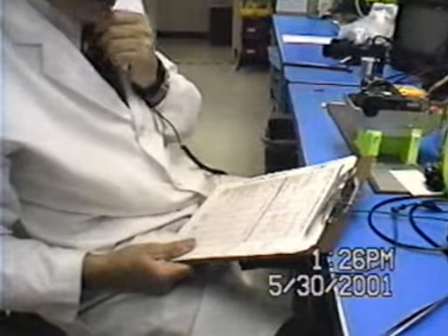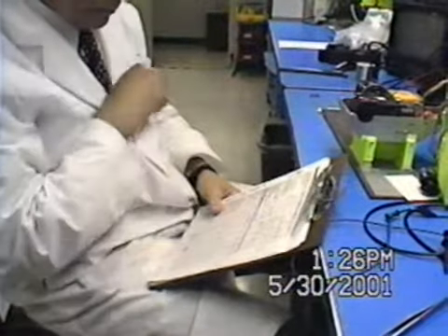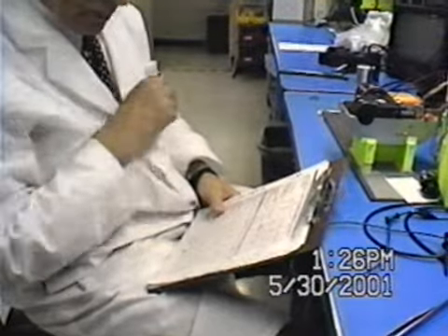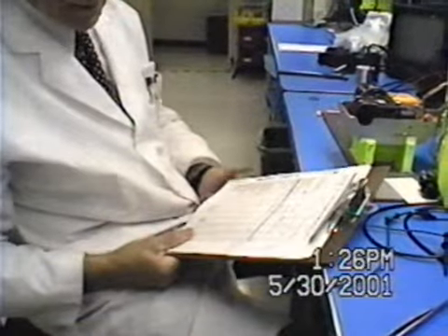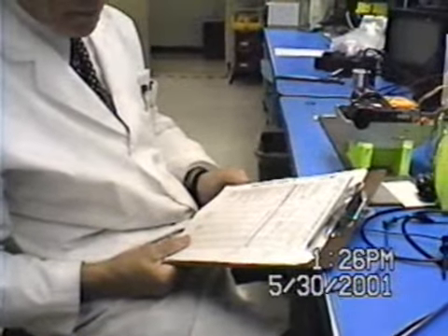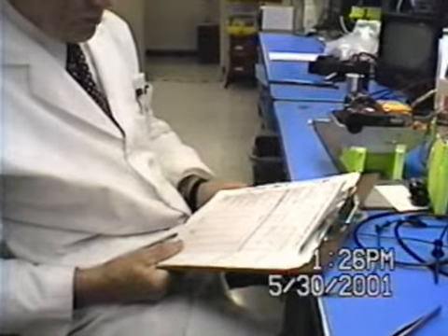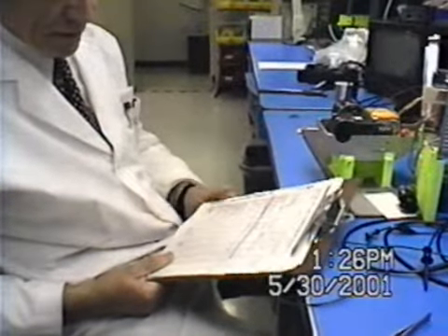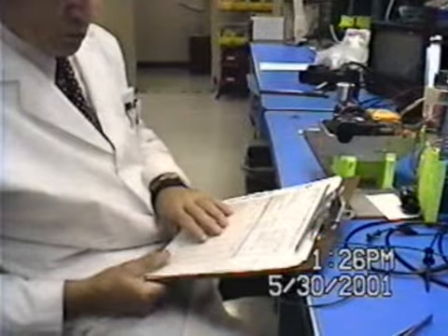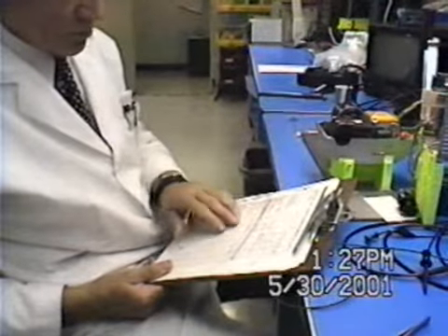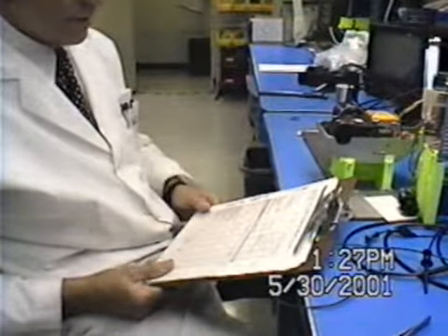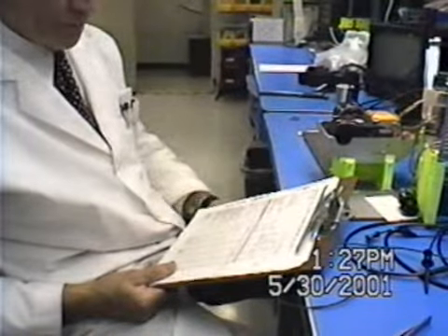We put in 3.3 mega ohm, and we got 1655 Fahrenheit, and we adjusted it up to 1662, which is equal to the 906 actual black body radiance temperature.